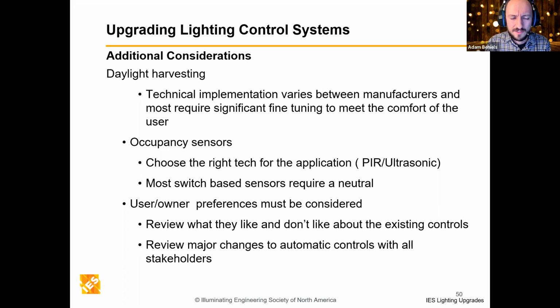Ben's touched on occupancy sensor tech. Really choose appropriate tech. Some sites don't want to use ultrasonic at all, which can limit how well you can use PIR sensors. Ultrasonic is fairly sensitive to ambient conditions. If you place them near air vents or loud equipment, it can make them hard to calibrate correctly. For switch mount PIR sensors in smaller rooms in existing buildings, often there's no neutral running to the switch, so you have to find sensors that run without a neutral. They do exist, but you just can't spec anything.